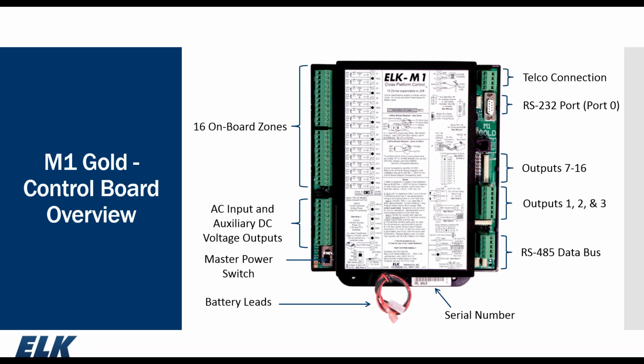All right, the M1 main board is what we're taking a look at right now. The green terminal blocks here on the left and the right-hand side are called Phoenix connectors. They are removable. So in a worst case scenario, for some unknown reason or catastrophic something happened, if you needed to remove the M1 board, you wouldn't have to disconnect any wiring except for the battery leads. You could take the terminals off, replace the main board, connect with your computer, and be back up and running in just a very few minutes.